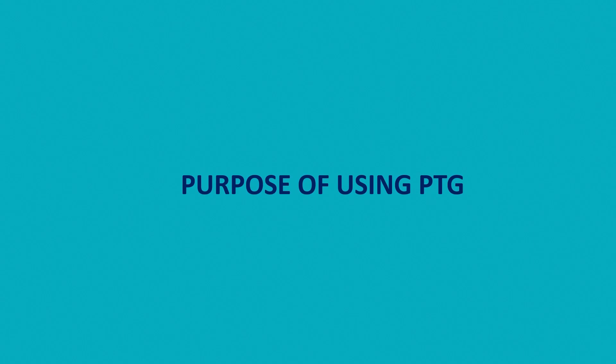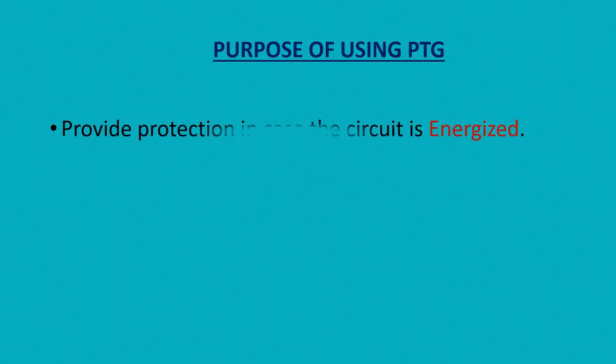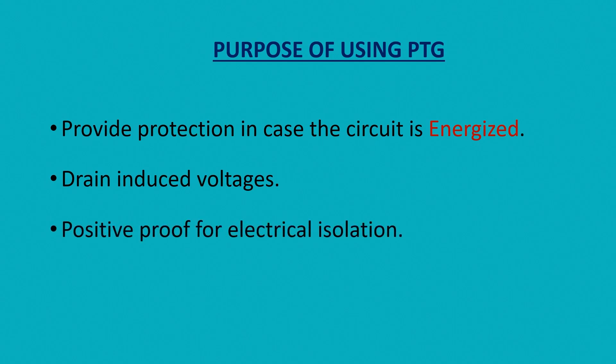So what is the purpose of using portable temporary grounds? PTGs provide protection to the worker and the equipment in case the circuit is energized by mistake. PTGs drain electrostatic and electromagnetic induced voltages. PTGs provide positive proof for electrical isolation. PTGs provide bonding.